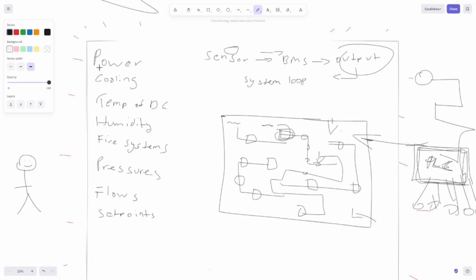What a BMS mainly shows is power, how much power you're having in the data center, the cooling capacity in the data center, the temperature, the humidity, fire systems and emergency systems, pressures of all the different equipment in the data center, flows, which is usually from the chilled water coming from the chillers, and set points.